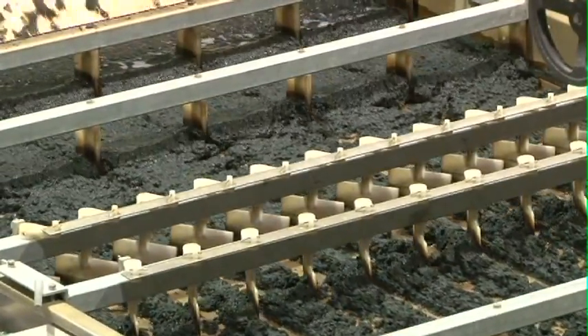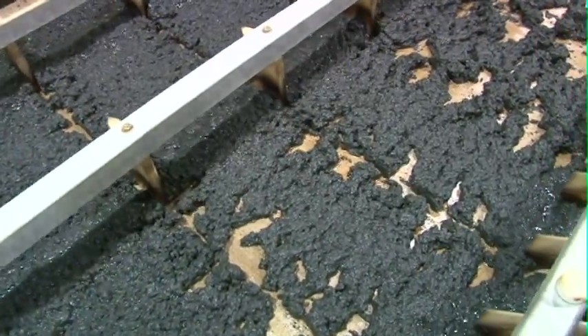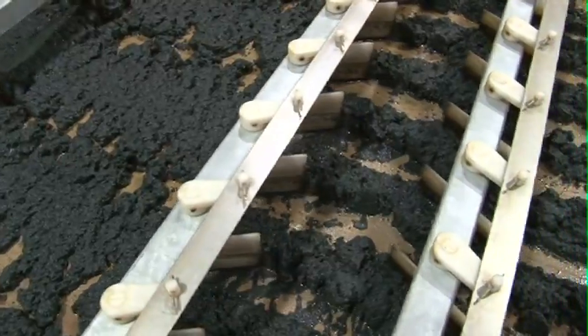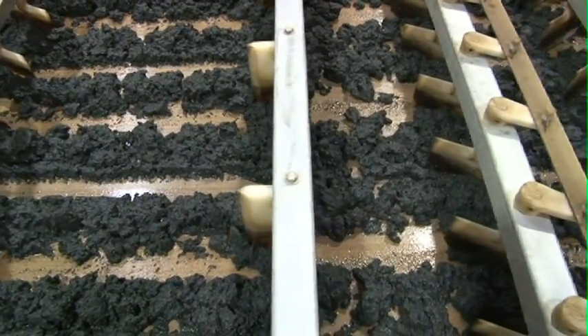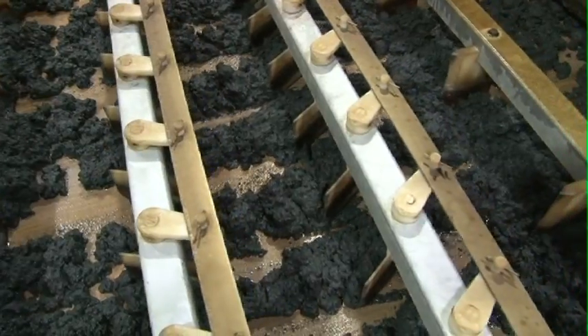Sometimes in the summer we run more than that. One of the technologies that we were not in tune with was the paddle wheel and how it evenly distributes the sludge onto the gravity belt. In the beginning we knew nothing about it and didn't quite understand how to utilize it, but after working with it for a couple of weeks, you get in tune with how to make it work. The adjustment of it — the speed — really evens out the sludge on the belt itself, making for a nicely, evenly distributed sludge and cake off the press. There are many different types of modifications you can make on the belt press, between speeds of belts, speeds of press, and the feeder box, to achieve many different types of consistencies within the sludge.